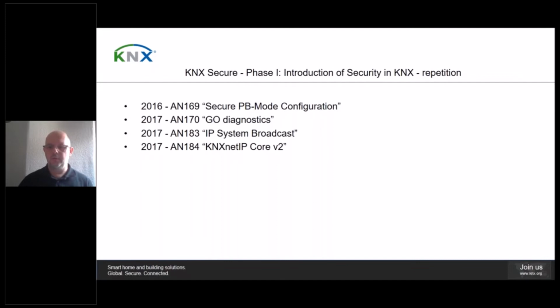KNX IP Core version 2. That was application note 184. This introduces TCP. As for secure unicast connections, KNX IP tunneling and KNX IP device management, it is important that the packet order is maintained, because packets, remember, with the wrong sequence number will be rejected. Additionally, this application note introduces a new search request extended, which allows limiting the responses to devices in programming mode or the devices with a given MAC address.